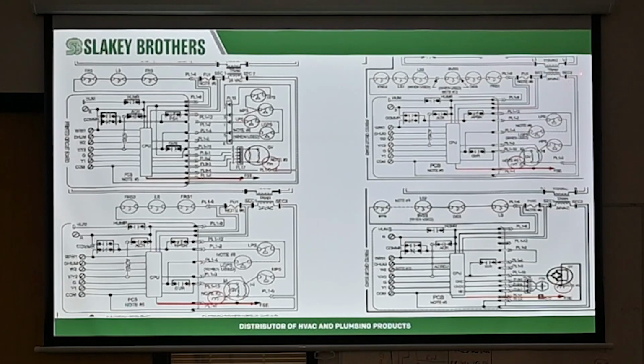When you look at your 24 volt circuit up in here, you got your section 1, which is your hot leg, and then your section 2. As soon as this touches metal right here, that grounds out the transformer already as well. So that's how come, as soon as you take the ground wire from your appliance cord and just screw it into the sheet metal of the unit, it grounds out the rest of the unit.